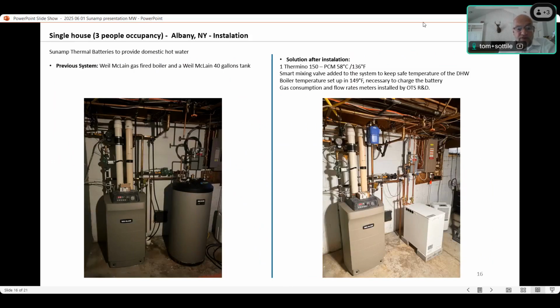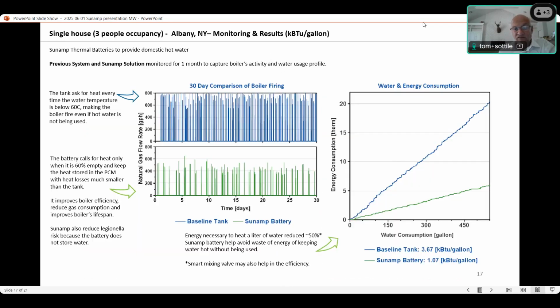We can also improve the efficiency of gas-fired equipment. This is a project we did with NYSERDA under a technology transfer grant, where we measured the gas consumption to produce hot water and the cycle rates using a standard Ultra condensing boiler with a standard indirect tank. We replaced that with our thermal battery, and we compared the cycles and gas consumption. We showed a 50% reduction in the amount of gas consumed to produce the same amount of hot water. This is attributed mainly to the reduction in cycle rates. The blue is every time the boiler fired on the indirect. The green is every time it fired with our thermal store.